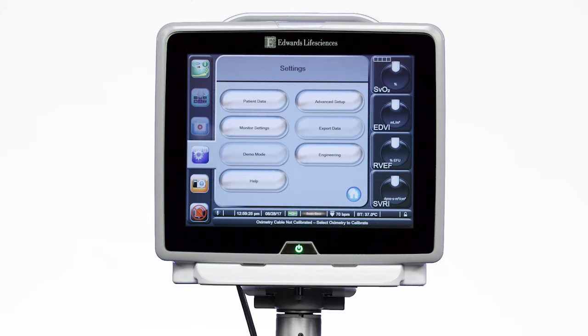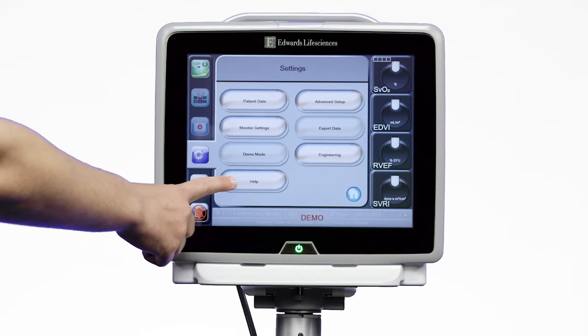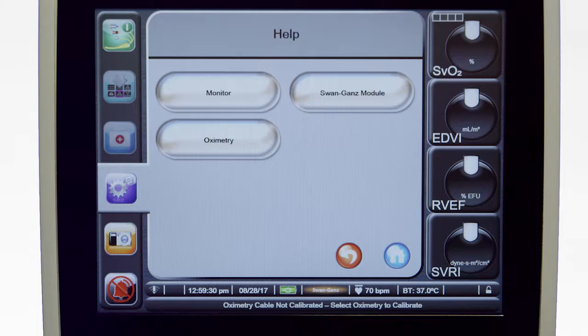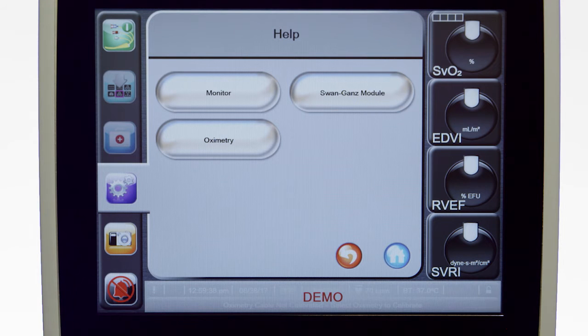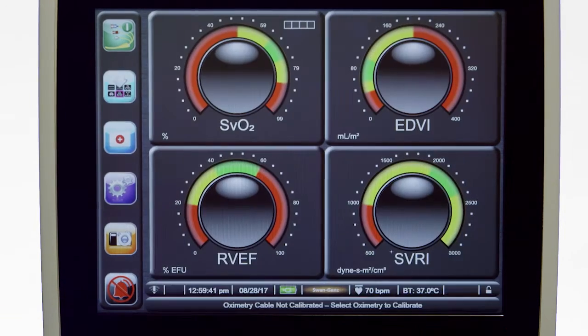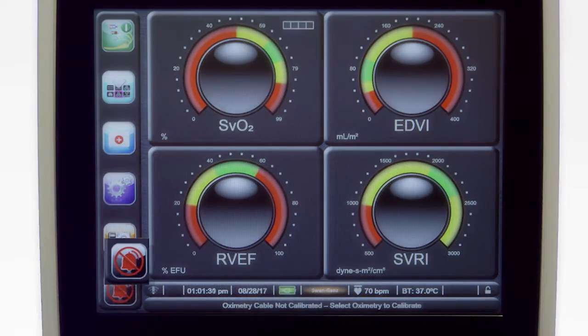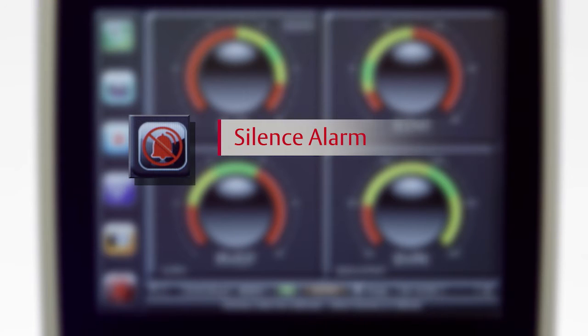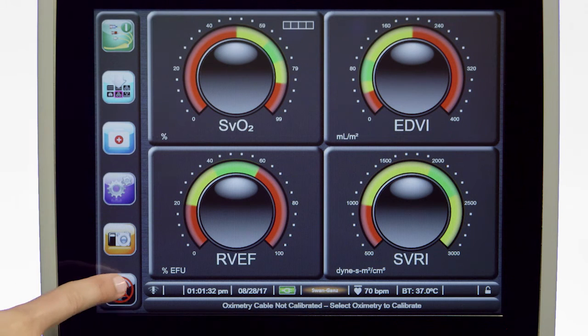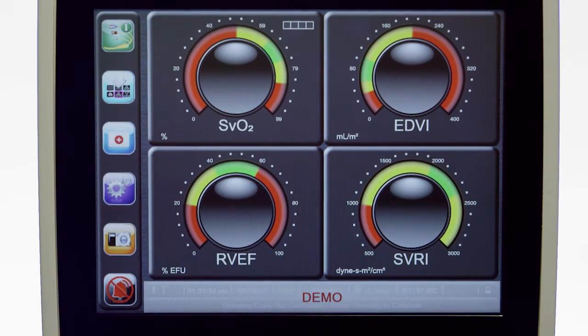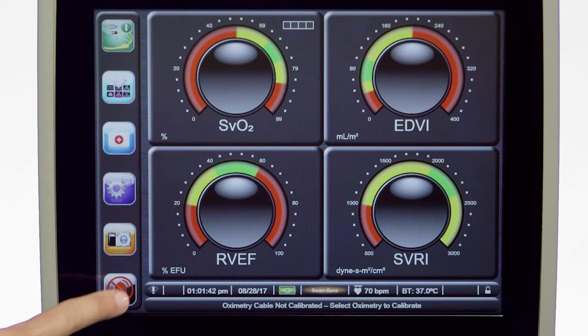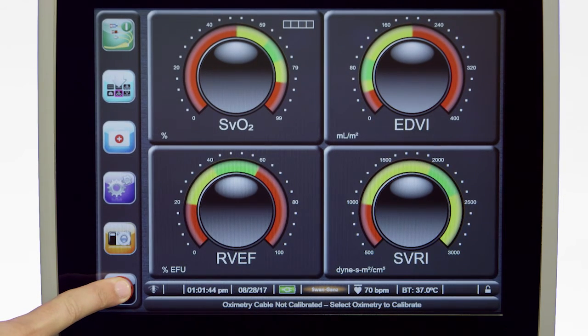For detailed information on a variety of topics, simply press the Help button. It takes you to a screen that directs you to additional information on specific topics. Anytime you wish to return to the monitoring screen, just touch the blue Home icon. Touching the Silence Audible Alarm icon will silence any alarms currently activated on the unit for a period of 2 minutes. Touching this icon for 3 seconds allows you to suspend monitoring.